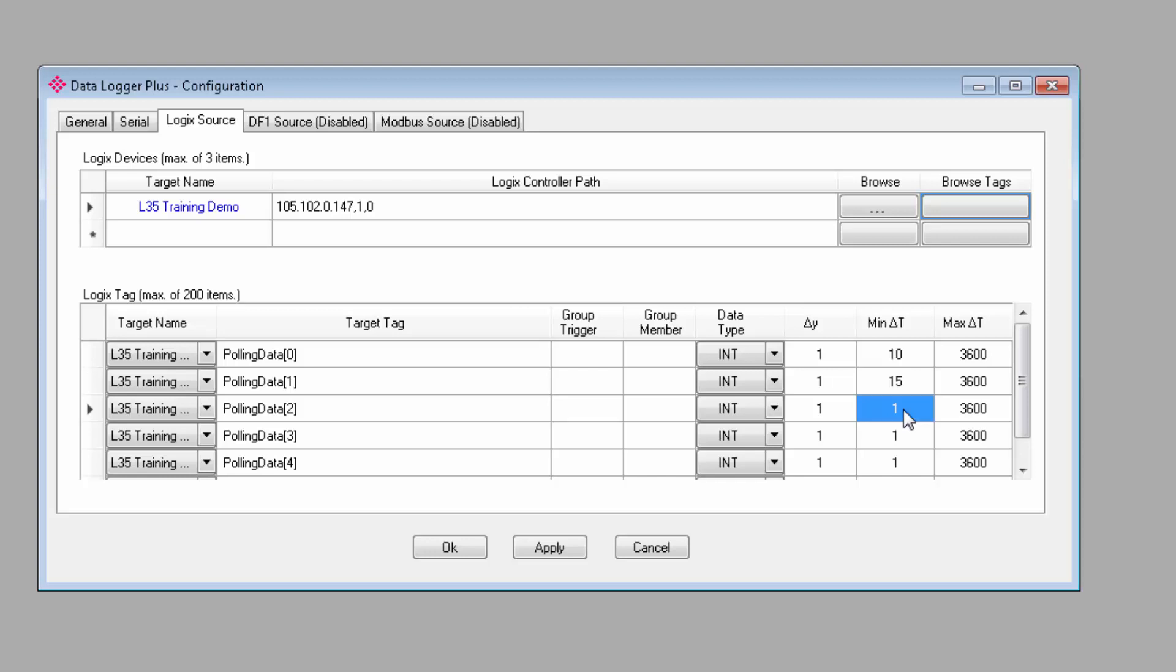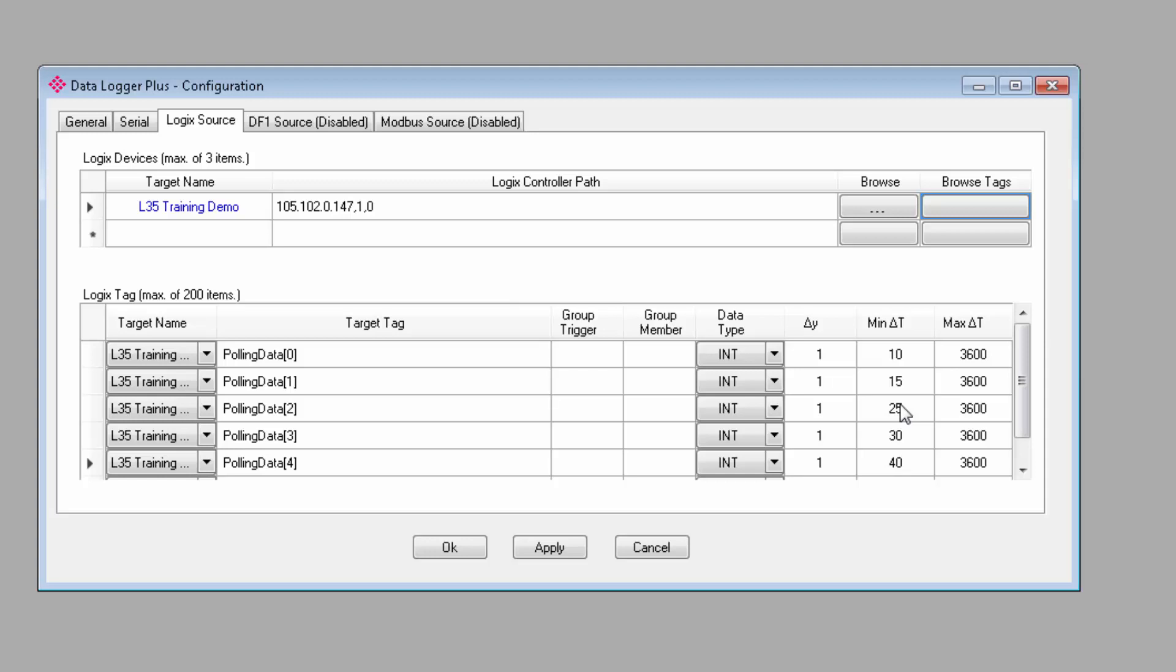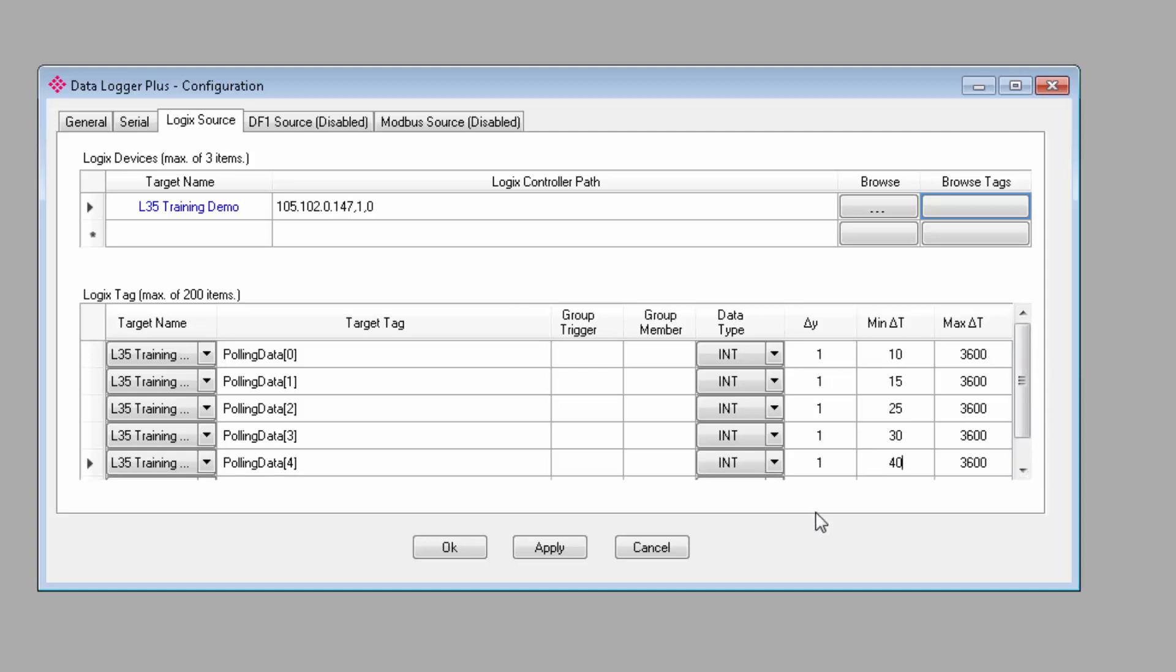Time units here are in seconds. So if you set this to the minimum of one second between logs, you could log data for a tag once every second, provided the tag value kept changing at least once every second. Unless you're monitoring something where every little change is critical, you don't really want to do that. If the variable that you're monitoring is something that changes rarely, or if it's a binary, you might leave the change value at 1. If it's something that changes more often or is more volatile, you might increase it to 10, 100, or whatever would be a significant enough change that it would be worth logging for your application.